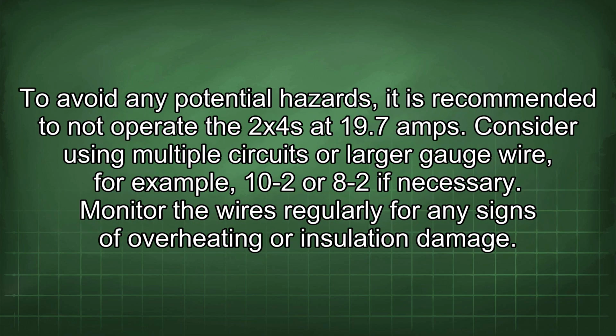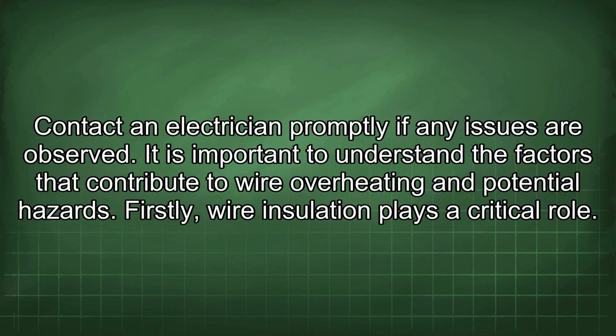To avoid any potential hazards, it is recommended to not operate the 2x4s at 19.7 amps. Consider using multiple circuits or larger gauge wire, for example, 10-2 or 8-2 if necessary. Monitor the wires regularly for any signs of overheating or insulation damage. Contact an electrician promptly if any issues are observed.